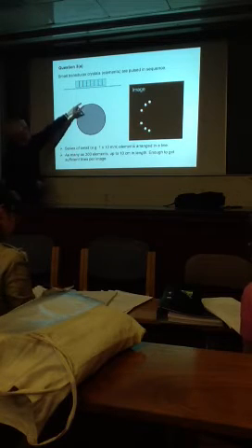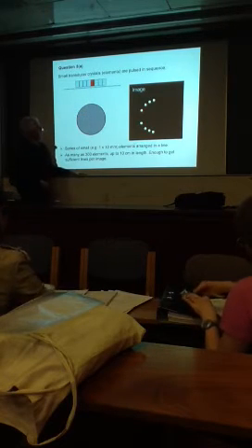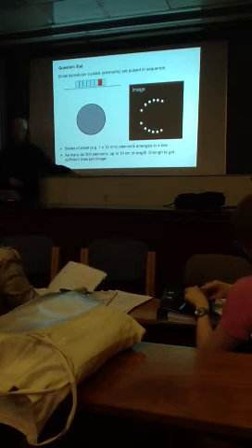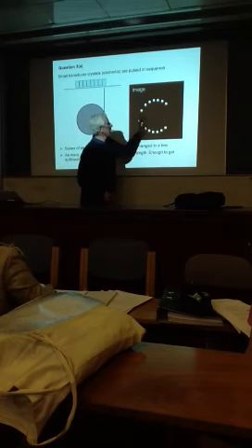So we have an array of transducer crystals, a much larger number than I have in my animation here, and I illustrate this as if we're pulsing one at a time. We send a beam downwards, and thus we measure the echoes that come back along each line of sight, and we construct a rectangular image.